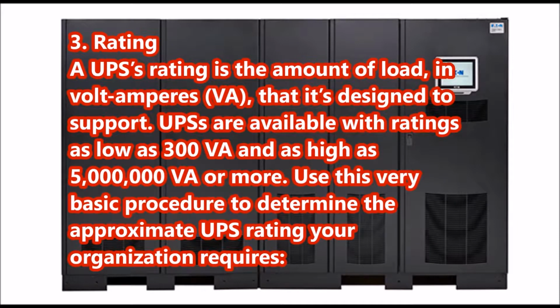Rating. A UPS's rating is the amount of load, in volt-amperes (VA), that it's designed to support. UPSs are available with ratings as low as 300 VA and as high as 5 million VA or more. Use this very basic procedure to determine the approximate UPS rating your organization requires.